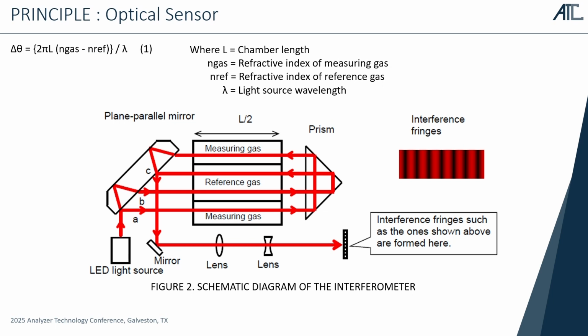And this is about the sensor principle for the optical sensor. Again, this optical sensor is to measure the refractive index of the target gas. And then there is a relationship between the refractive index and the calorific value, BTU value. So if we measure the refractive index, then we can measure the BTU calorific value. And then, as you can see in the structure, there is a measuring gas chamber here and here, and then there is a reference gas chamber here.